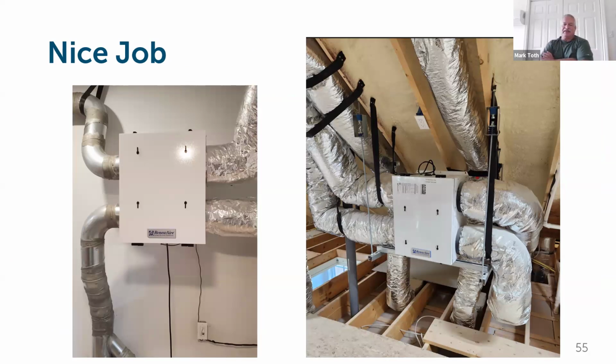The system on the left here, actually, this was a job that is not too far from where I live here in New Hampshire. A few years ago, I got a call on that job when he was done that the system was too loud. This is one of the ones, for some reason, that duct system was having some strange noises moaning through that duct system. It was very weird. So we went there, took out on the left-hand side those two hard elbows, top and bottom.